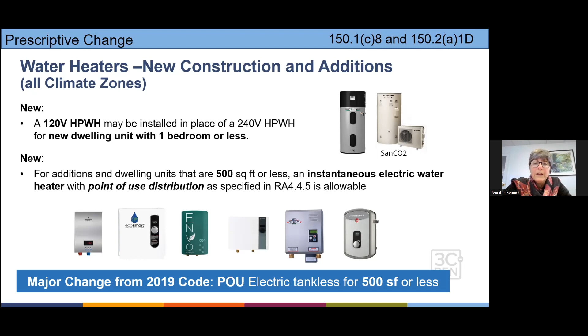So this really is to address the small additions, ADUs, tiny houses, those things, realizing that for something as small as 500 square feet, it was not as cost effective and sometimes quite problematic to get a heat pump water heater for that size of dwelling. However, the electric on demand, the instantaneous type, seems like such a logical solution. But under prior code cycles, you couldn't use that type of water heater. So they've made this allowable now when you meet these special requirements of 500 square feet or less and point of use distribution. And there's what a bunch of them look like. They kind of look like the on-demand gas units, only there's no gas and no flue that has to be dealt with. So they're quite cost effective.